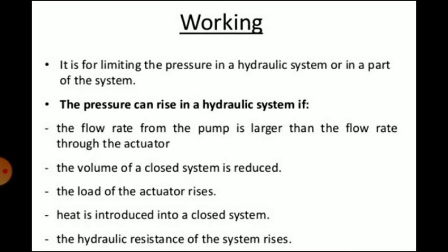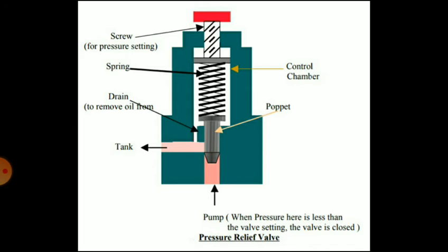So it consists of a casing fitted with a cone or spool which blocks the flow of pressurized fluid due to spring force. The spring force can be adjusted by tightening and loosening the screw. When the resulting force F exceeds the spring force, the cone or spool moves in the opposite direction to the spring force and opens the connection between inlet and outlet. The pressure level which is to be maintained is thus controlled by spring force.